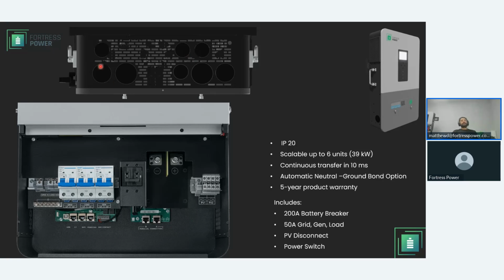On top, you have the knockout holes, which would be perfectly well seated on top of a wireway. Or you could hang the inverter on the wall as well, and then feed the AC on the left side and the DC on the right side. The knockout hole on the side is a 1.5-inch knockout hole. So just take that into consideration when installing this system.